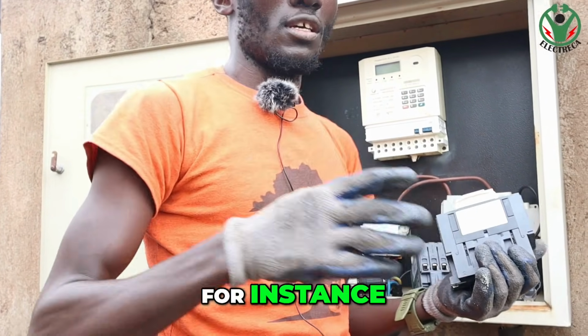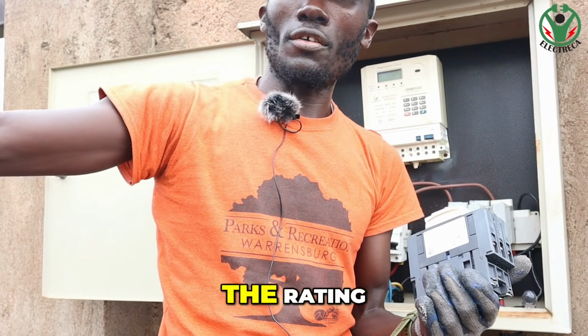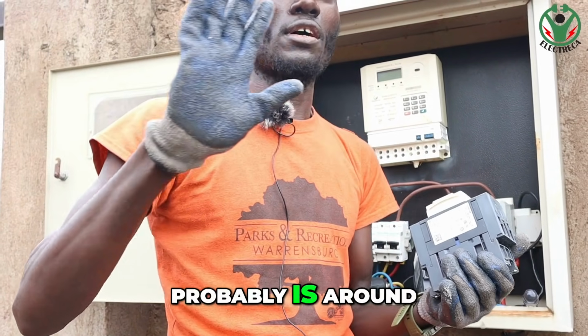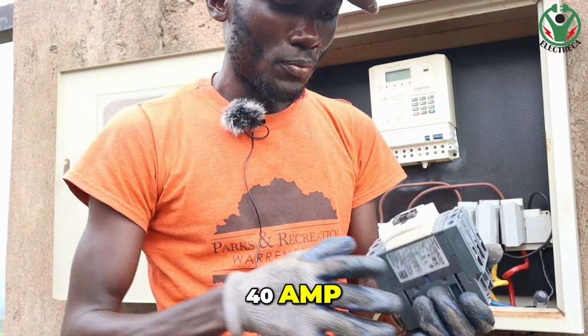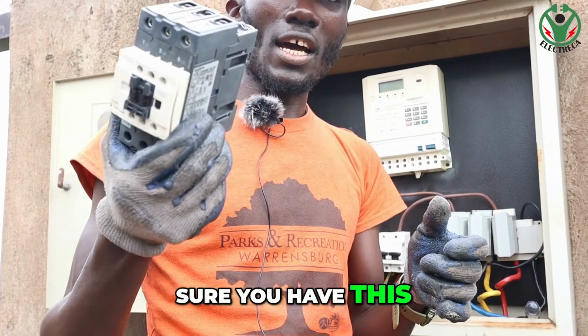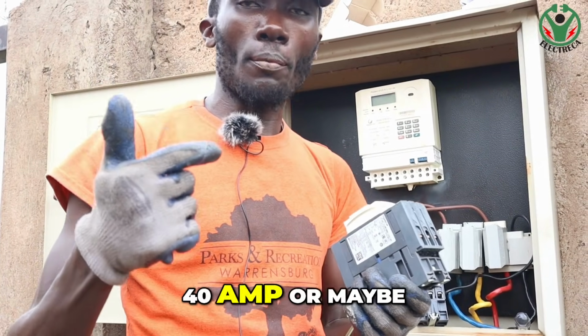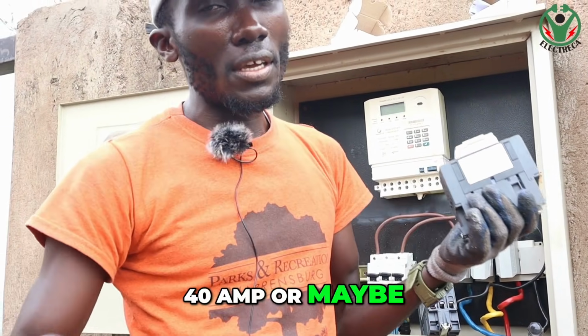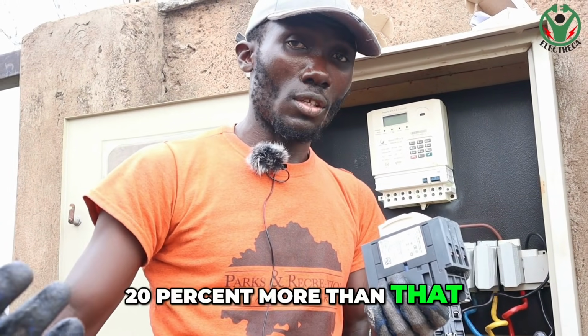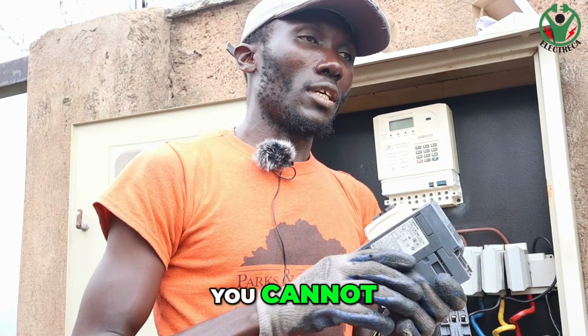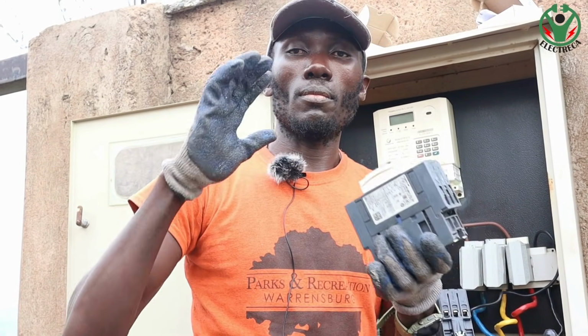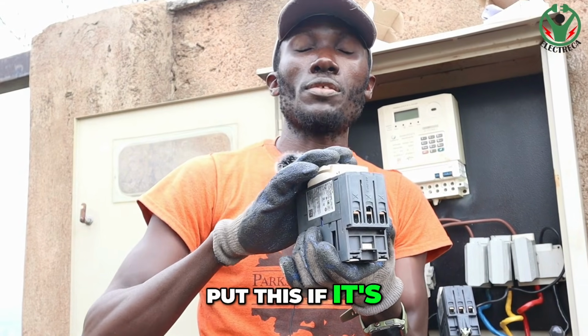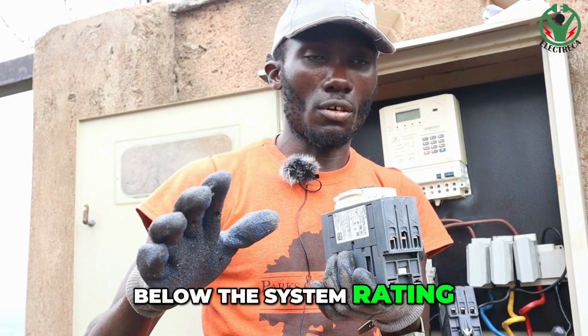So, for instance, if the system rating is around 40 amp, you must make sure you have this guy either equivalent to 40 amp or maybe 20% more than that, okay? You cannot put this if it's below the system rating, okay?